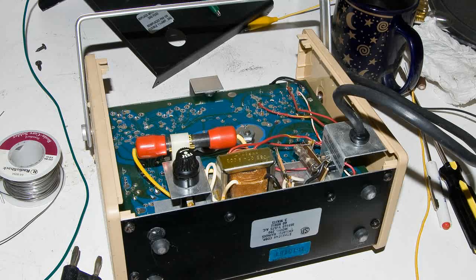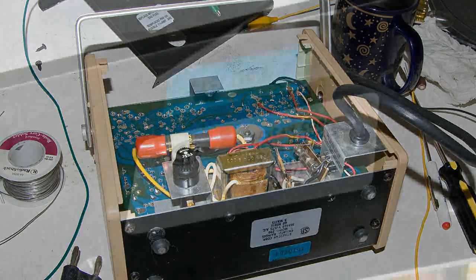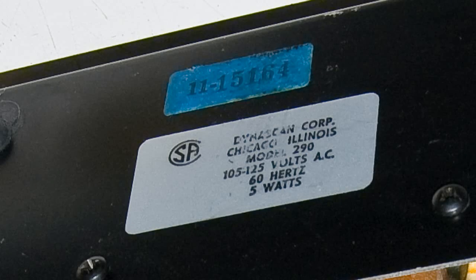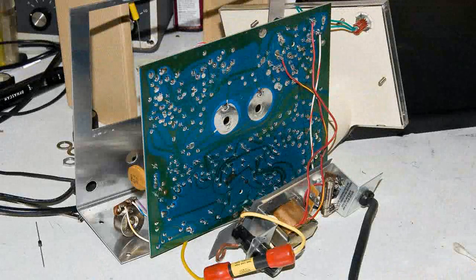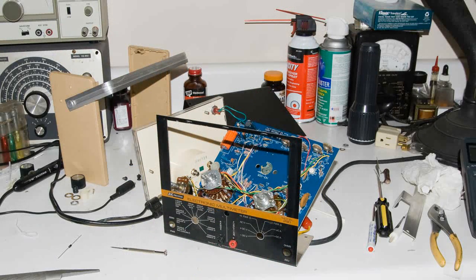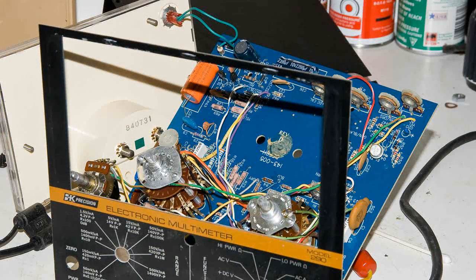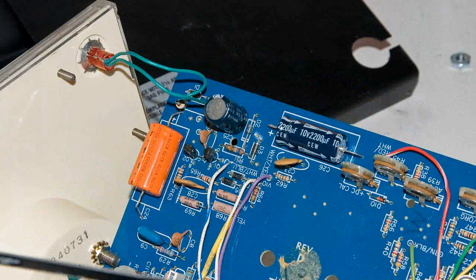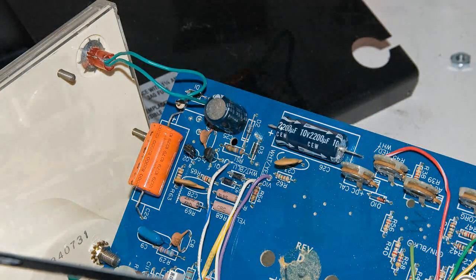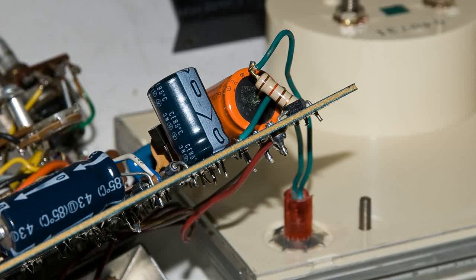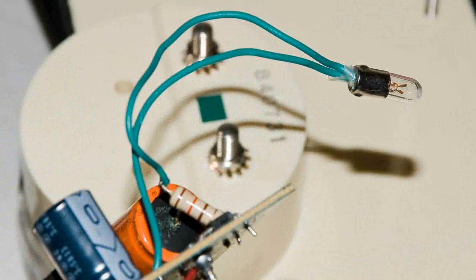Here's the back side of it, and here's a closer look at the stickers that are on the bottom of this meter. Now here I've torn it apart even more, looking for obvious burn marks or something like that, and didn't see anything. Now here's an overall shot of the front of this, and as I zoom in, it'll be very obvious that there's something not quite right with this. This is definitely not factory or original. And what has happened is the bulb is burned out.